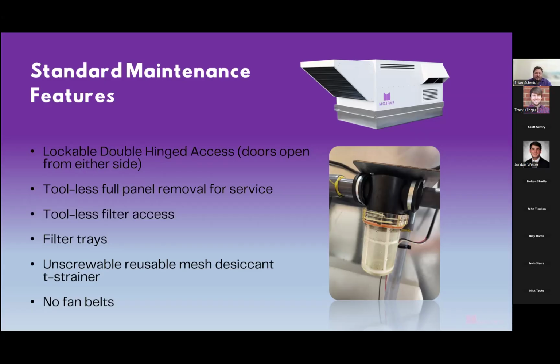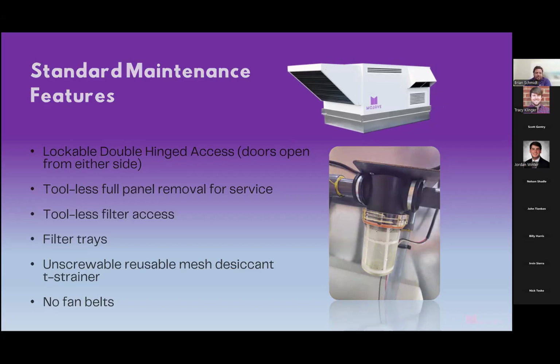The system will adjust if any of that salt is lost, and it's not going to be much because the volume in these T strainers is very low. But that is the only maintenance for the liquid desiccant system itself. Pads never have to be washed, never have to be replaced. The pumps, if they were to go out, would obviously need to be replaced. But the only preventative maintenance really is these T strainers, to ensure that those pumps don't get clogged up.